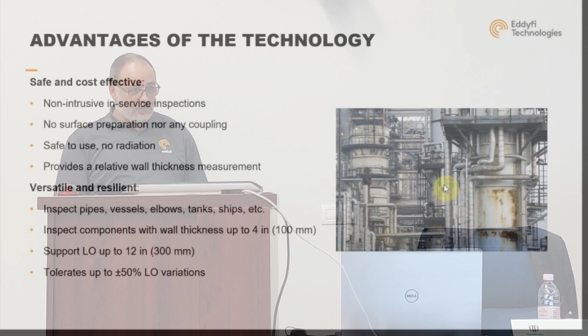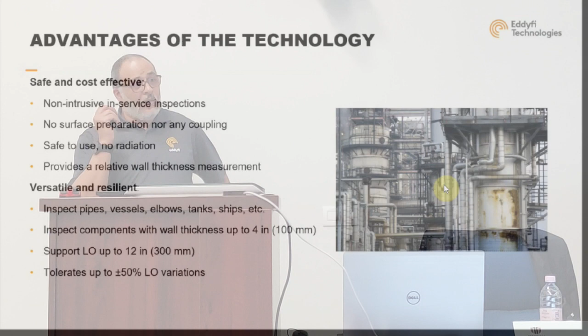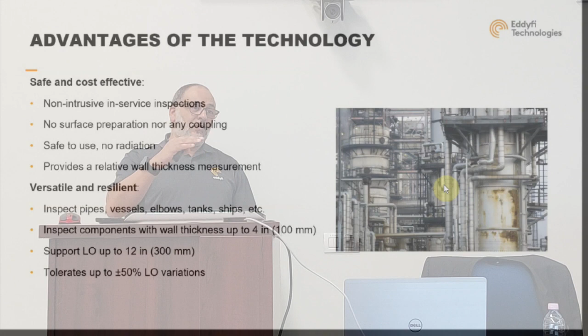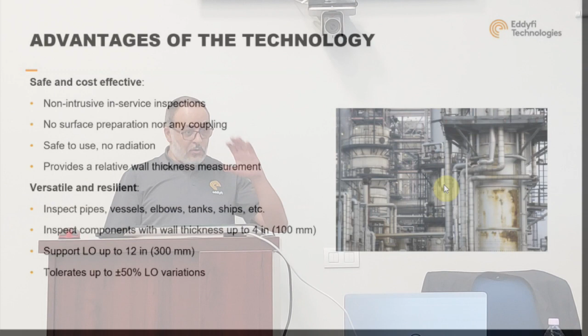Just one thing to take into account, an important thing to take into account: the measurement that will be given is a relative wall thickness measurement. So it will depend on what we call the footprint that I will cover in the next slide. It can be applied on piping, vessels, elbows, tanks, ships. We have a set of probes, so we can go up to 100 millimeter of thickness for the inspected component, and with the lift-off up to 300 millimeter, so 300 millimeter of insulation eventually. The technology is also tolerant to lift-off variation of plus or minus 50%.